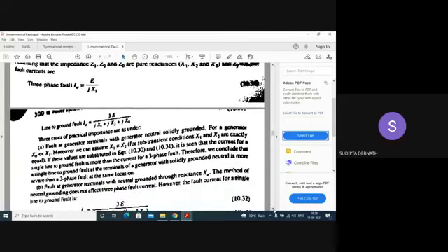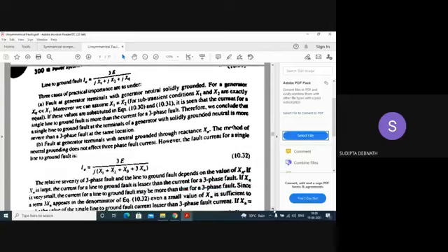Now we find out under what condition this single line to ground fault will be more and more severe, and under what condition it will be less severe. That will depend. It is always more severe if the neutral is solidly grounded, that means if there is no XN. Neutral impedance is considered as XN.